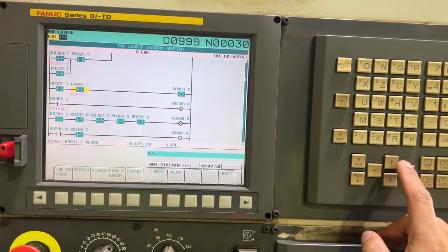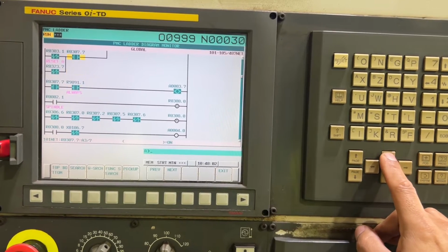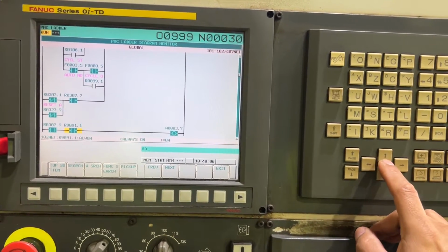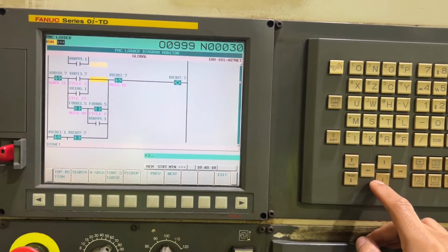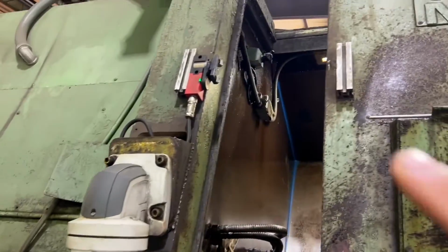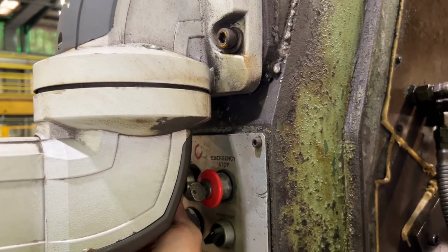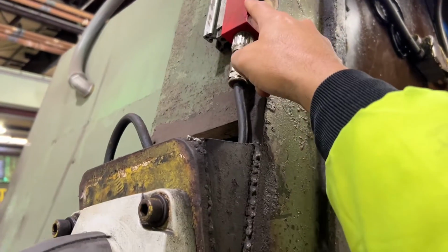So now we have this condition that is making that coil. So we need to review this condition that is on the top, but I know this is because we have the door selected in open and the door interlock is bypassed, so this is the condition that we need in yellow right here.